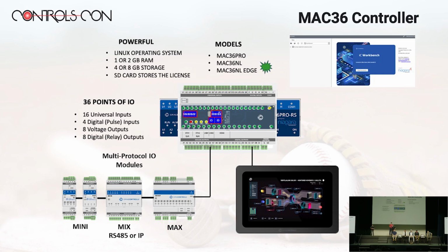We have some dip switches and a couple rotary switches, and you can use those to characterize the controller before you install it. So I can put multiple programs in a single Mac 36, and then the tech out in the field can take the cover off, select the dip switch he wants, and it runs a different program. Or he can use it to select different operating parameters. A real nice feature, it comes along for the ride, doesn't cost you anything extra, and doesn't add points to your Tridium.